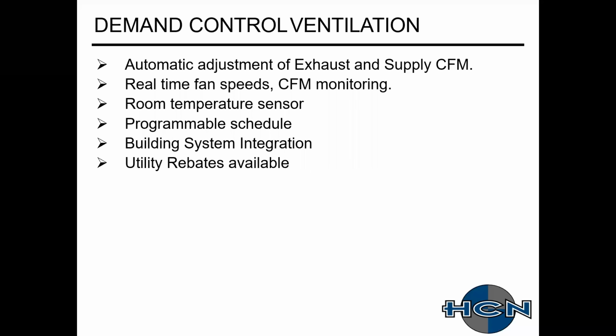And one more before we get too far. On the slide with the kitchen RTUs, the slide noted return air to the kitchen RTU. The IMC states that kitchen exhaust cannot be recirculated. It does not say that only kitchen hood exhaust cannot be recirculated. Can general kitchen return / exhaust be recirculated to the kitchen?